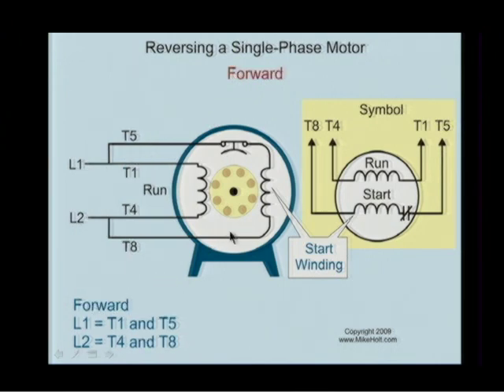Now, I want to go back and look at this electrically. This has line 1, so Mike, put a line 1 here and a line 2 here in the future. And then put a line 1 here and a line 2 here, so I can see that those windings are connected in parallel to each other. Is that right? Yes. So that means each winding right now would be, if this is 230, then that's 230 and that's 230. You guys agree with me?